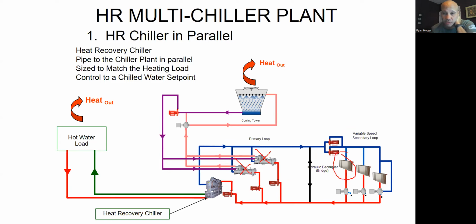Some of my zones need cooling, right, for their interior zones. I'm going to run the heat reclaim chiller. And this guy is going to send water out to them and take water back, right? But instead of being designed for a cooling tower, he's going to be designed to operate with the kind of water temperatures you need for your heating load. So this chiller is going to take the place of your boiler or your hot water heater. So this becomes extremely useful in places where you have almost year-round need for simultaneous hot water and chilled water.